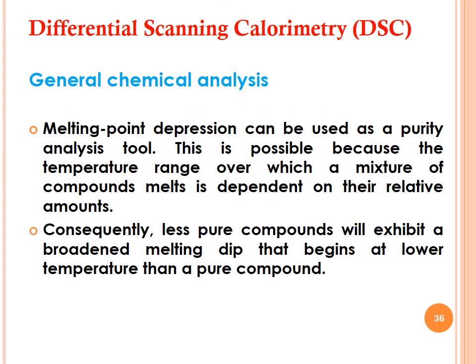General chemical analysis can also be done by DSC. Melting point depression can be used as a purity analysis tool, since the temperature range over which a mixture of compounds melts depends on their relative amounts. With impurities, the melting point decreases. Consequently, a less pure compound will exhibit a broadened melting dip that begins at a lower temperature compared to a pure compound, allowing purity determination based on melting point comparison.